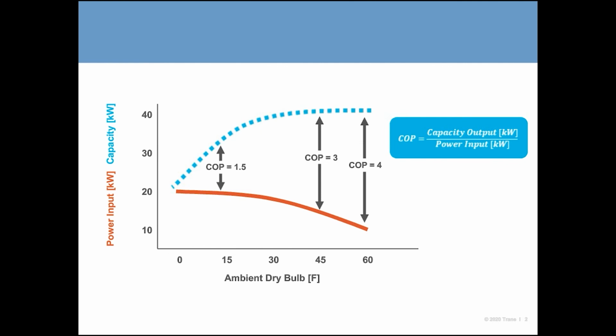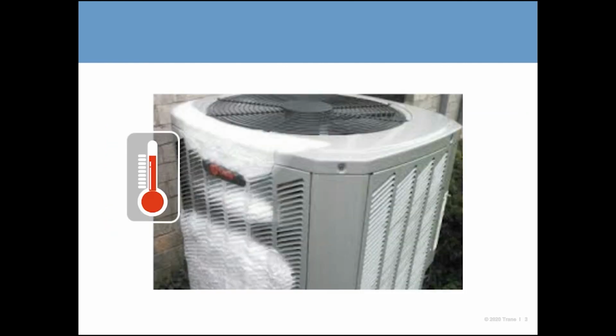Another thing that needs to be known from the manufacturer is defrost. All right, because there's going to be a defrost derate for each piece of air source heat pump equipment. And if you're not familiar with defrost, there's an outside coil that we're pulling BTUs out of the outside air. So you think of that, we're essentially cooling down the outside air outside. All right, and if that coil temperature is below the dew point, you'll start to condense. And if it's also below 32 degrees, it'll start to freeze.